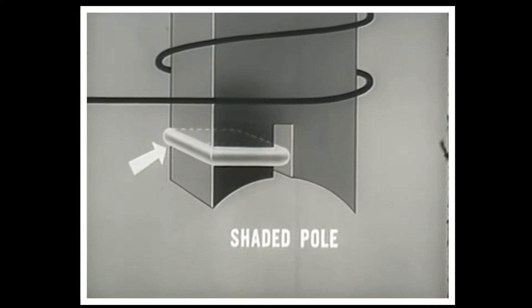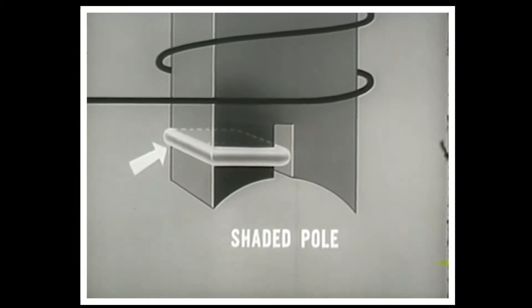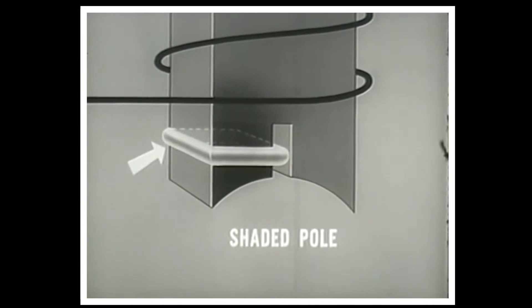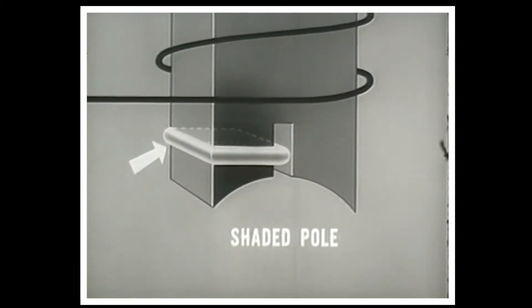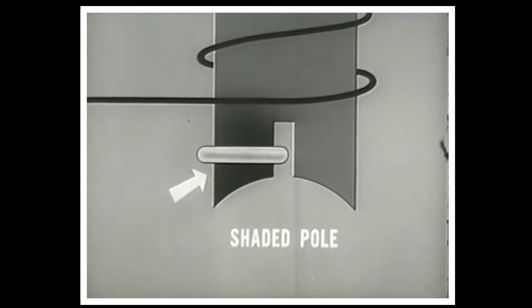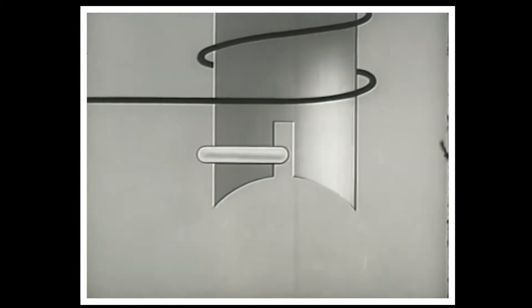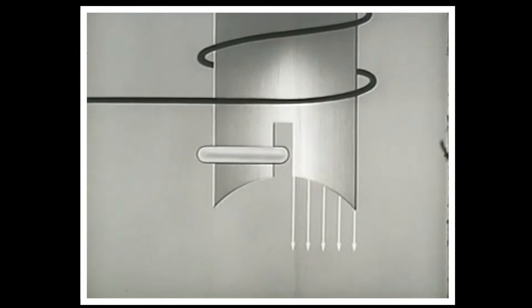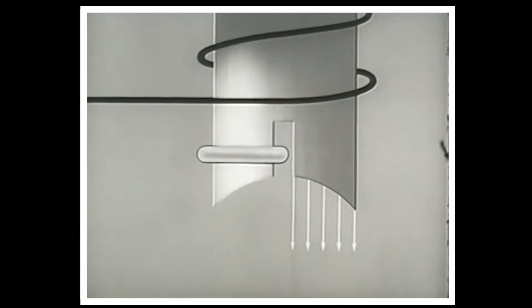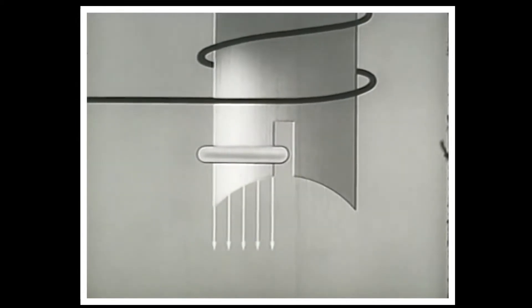One method is the use of shaded poles in the field. A shaded pole is attained by placing a copper ring in a slot over half the pole. The copper ring on the shaded half of the pole increases the inductance of that half, causing the magnetic field of the shaded half of the pole face to lag behind that of the unshaded portion, creating a rotational effect.